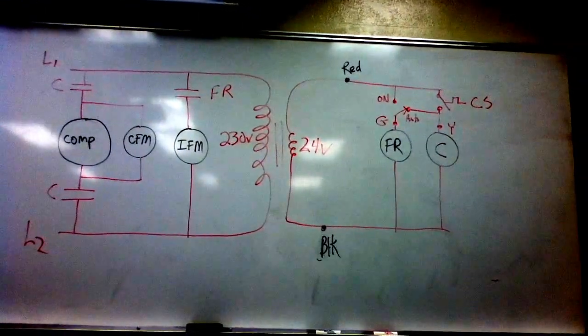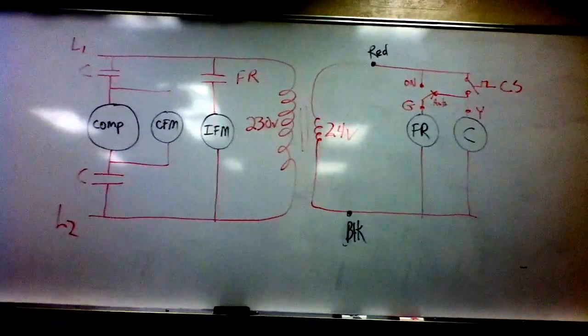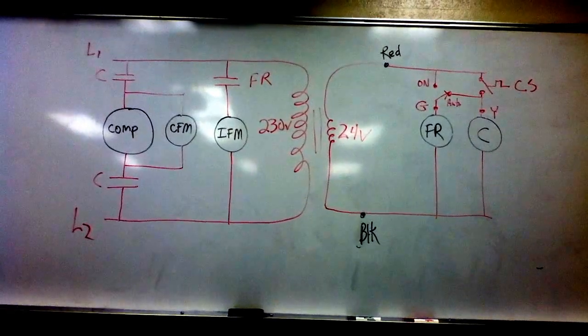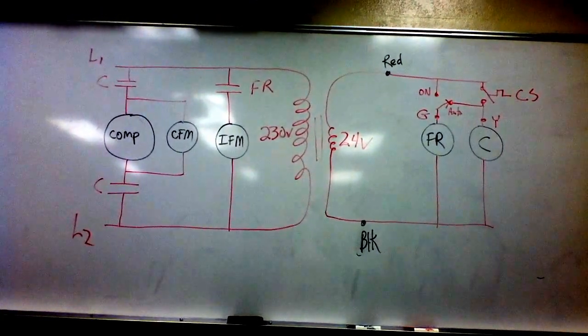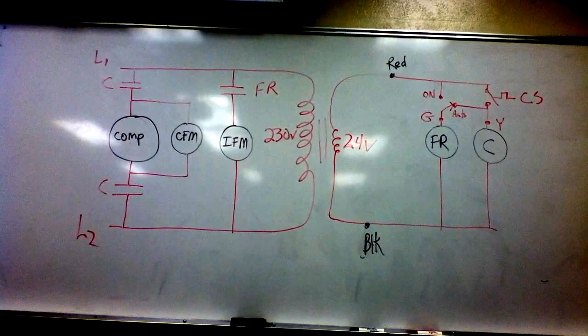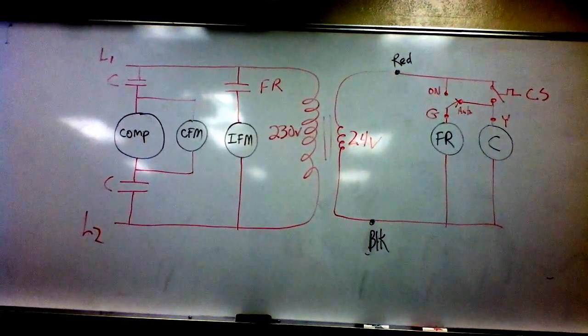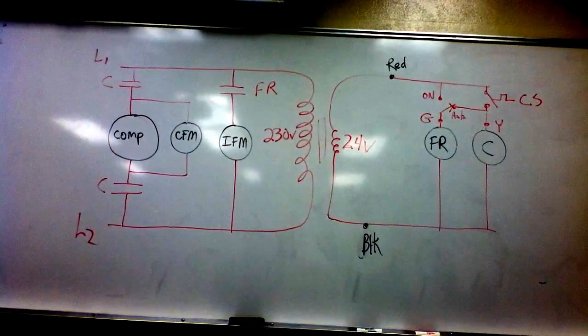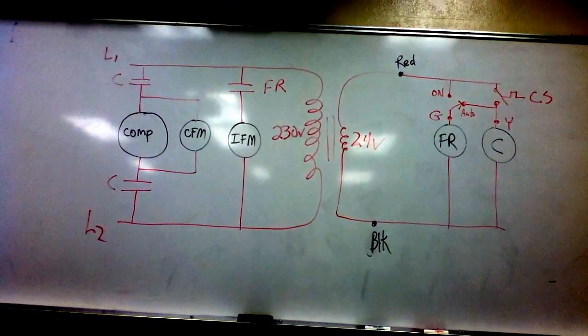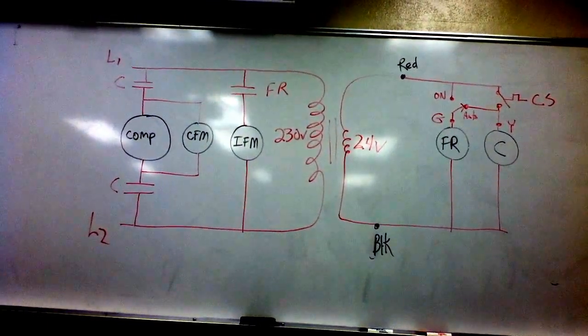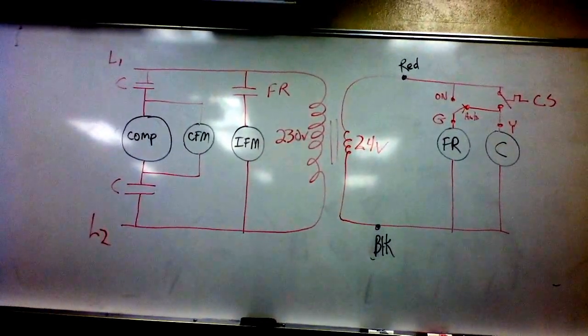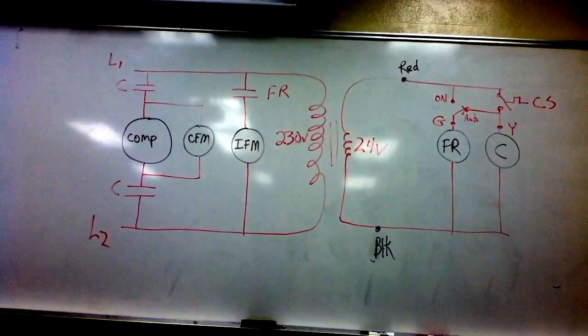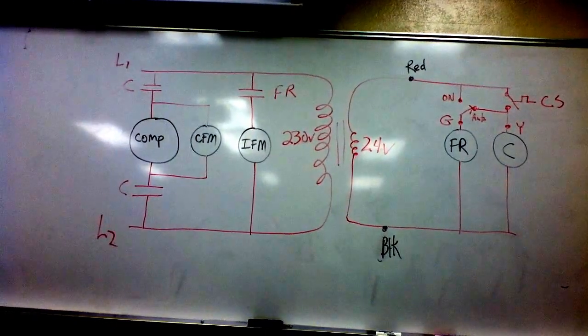Nothing will start until the thermostat closes. Then power comes down through the stat and splits. Part of the power goes to the fan relay coil and back to the other side of the transformer. Part of it goes through the contactor coil and back to the other side of the transformer. So the first thing that goes is the fan relay. Well, at the same time it does the fan relay, it does the contactor coil.